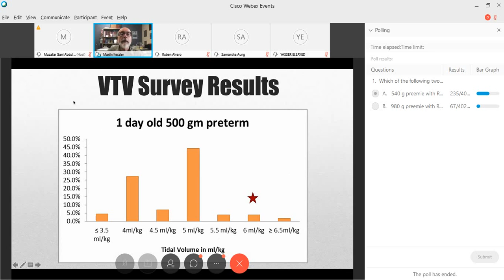Anyway, the bottom line is that indeed the tiny baby needs a larger tidal volume per kilo, which might seem counterintuitive until you realize that it's really about the effect of the instrumental dead space of the flow sensor, and that's seen here. So this is a study we did a number of years ago for babies less than 800 grams. And we looked at what tidal volume was associated with normal PCO2. In other words, when the CO2 was in our target range, what was the tidal volume? And in these extremely low birth weight infants, between 700 and 800 grams, the tidal volume was around 5.5 ml per kilo, as you might predict. But when you get to the other end of the extreme, the ridiculously low birth weight infant, that's a copyrighted term, you need more like 6 ml per kilo.